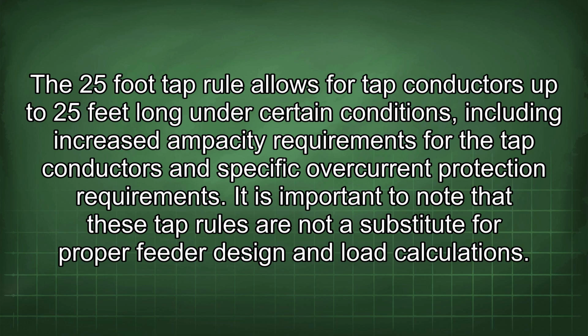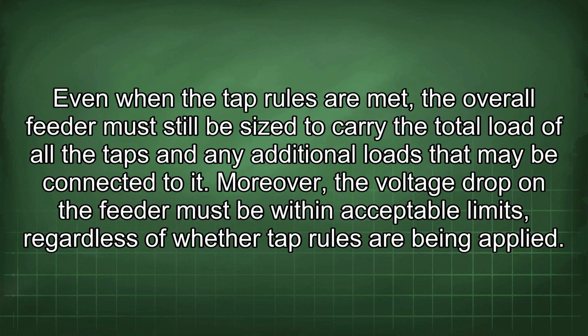It is important to note that these tap rules are not a substitute for proper feeder design and load calculations. Even when the tap rules are met, the overall feeder must still be sized to carry the total load of all the taps and any additional loads that may be connected to it. Moreover, the voltage drop on the feeder must be within acceptable limits, regardless of whether tap rules are being applied.